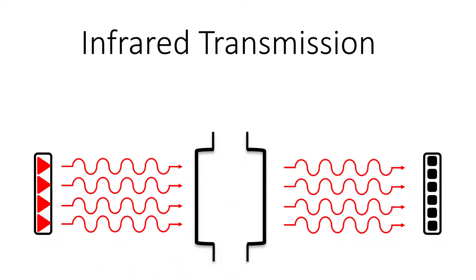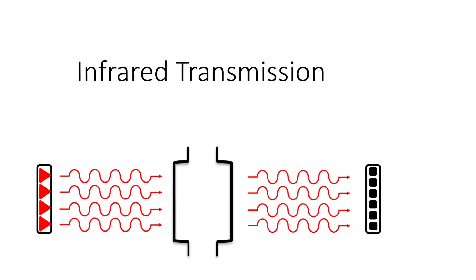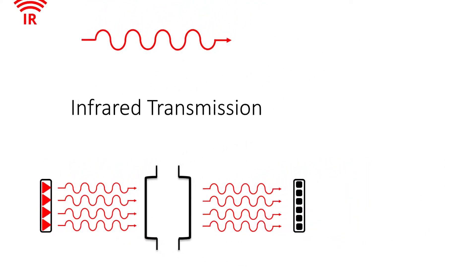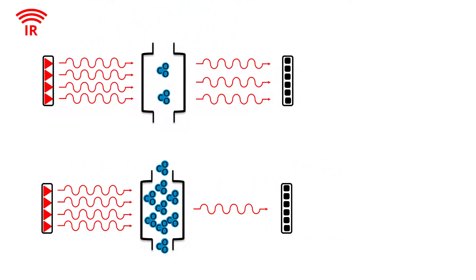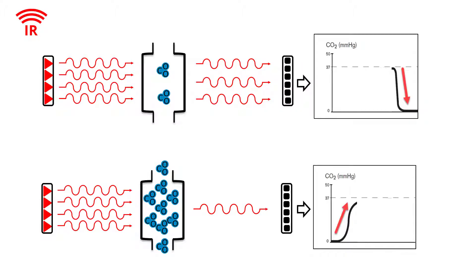For both measurements, the measurement principle is infrared transmission. Infrared waves fall on a photodetector. The more CO2 present in the respiratory gas, the more infrared rays are absorbed. The monitor uses the information from the detector to display the capnography.